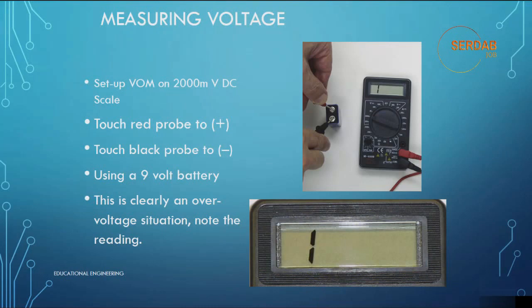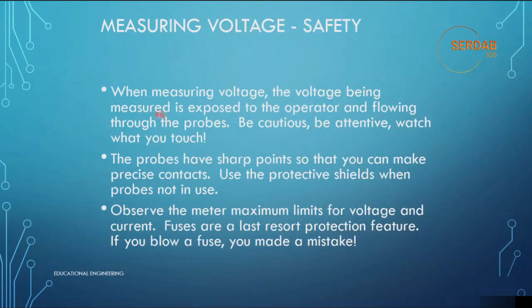Now let's talk about safety in measuring. When measuring voltage, the voltage being measured is exposed to the operator and flowing through the probes. Be cautious, be attentive. Watch what you touch. You shouldn't touch the probes while measuring voltage. The probes have sharp points so that you can make precise contact. Use the protective shields when probes are not in use, so that they won't harm anyone.